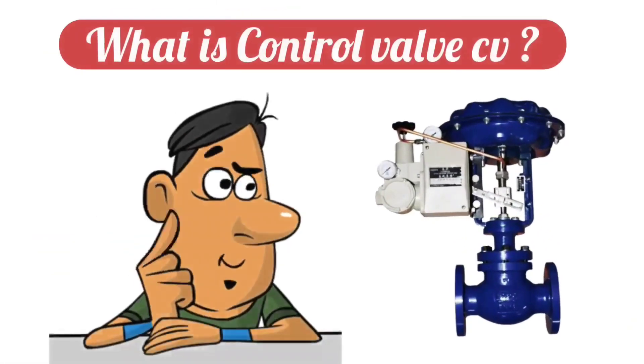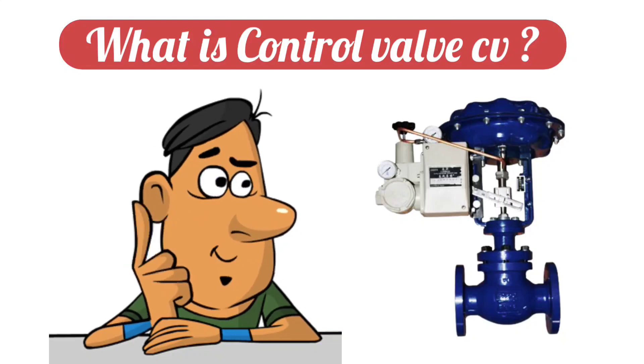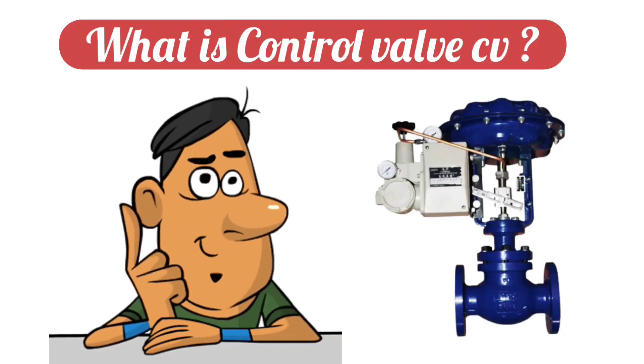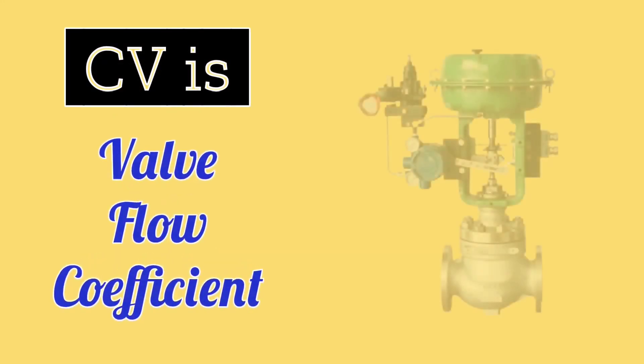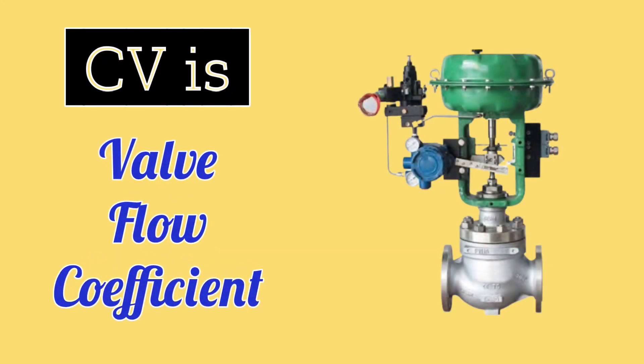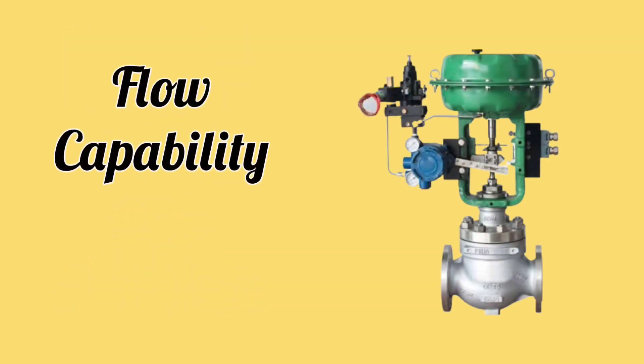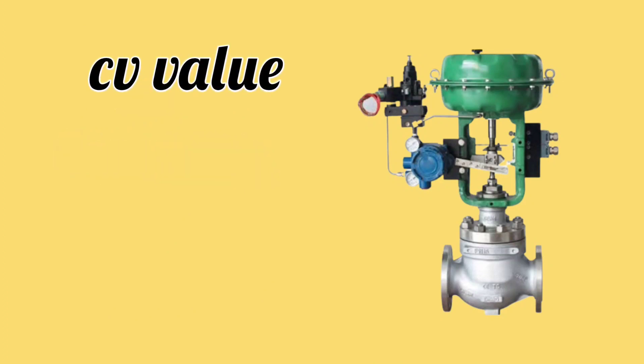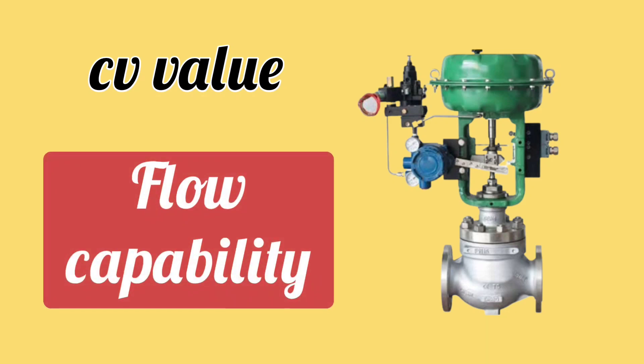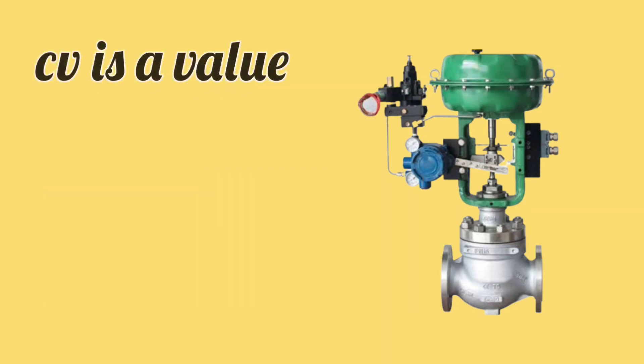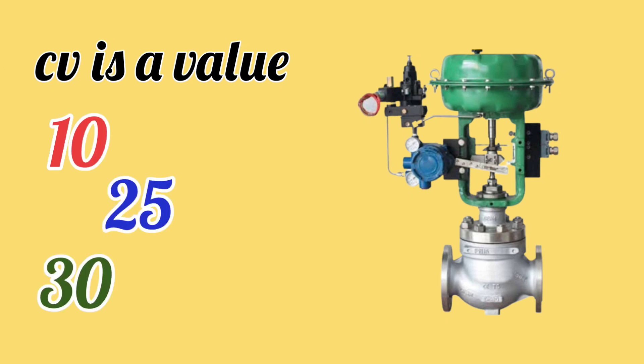What is control valve CV? Friends, if understood in simple language, CV is called the valve flow coefficient — meaning it tells the flow capability of the valve. The higher the value of CV, the higher will be the flow capability. CV is a value, such as 10, 25, or 30, and it does not have any unit.